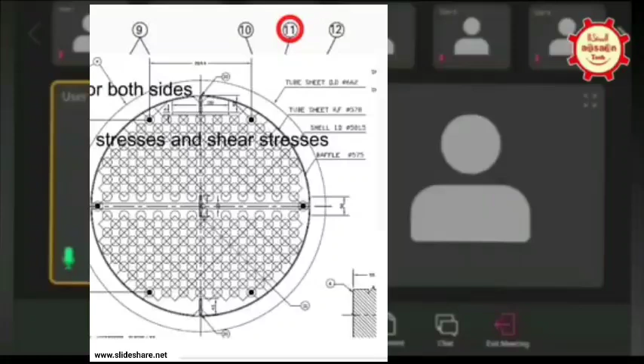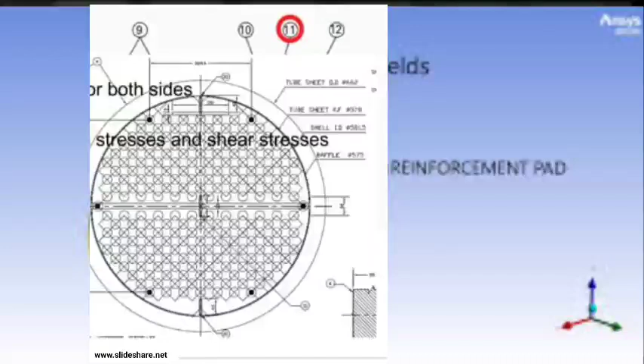So now 16 mm, if I consider 1.5 times, it will come to 24 mm. And then the tube sheet has extra RF which is not calculated as part of the thickness of the tube sheet. One is the lower RF, one is the higher RF. Suppose the higher RF thickness is 7 mm and the lower RF thickness is 5 mm, just assuming now.